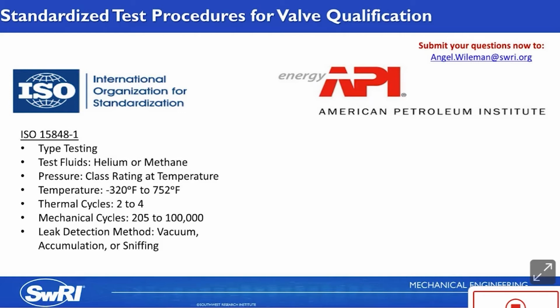Now, if you were to qualify a valve from -320 to 750, you would split this up into a complete qualification from room temperature to high temperature, followed by a full qualification from room temperature to -320. You wouldn't go straight from the cold to the hot. The number of thermal cycles for this test ranges from 2 to 4, depending on the endurance class.